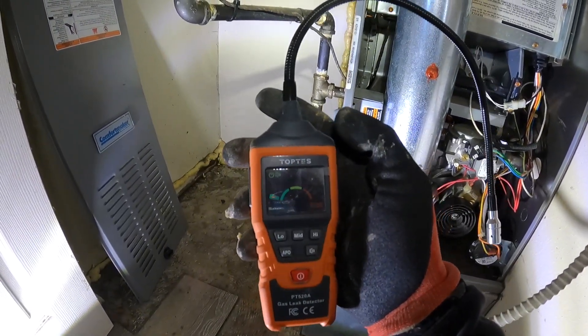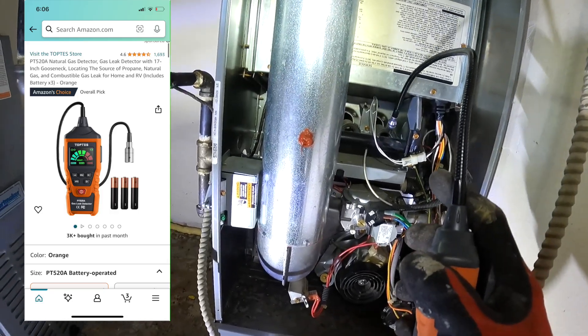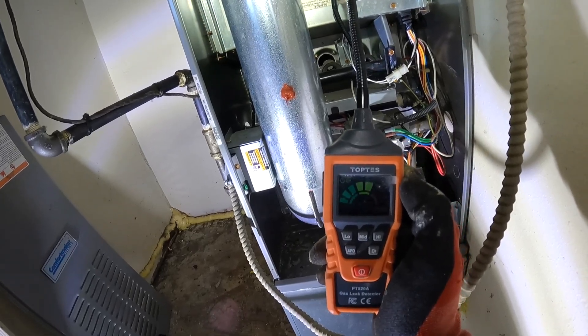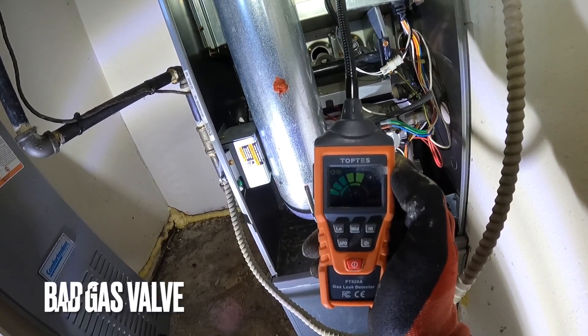For that, I use my TOPTES — link down in the description, also on my Amazon page. Stick this right there, give it a second. And you can see that it's leaking through. So this gas valve is leaking gas through.